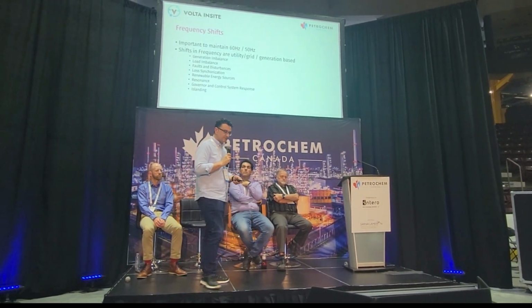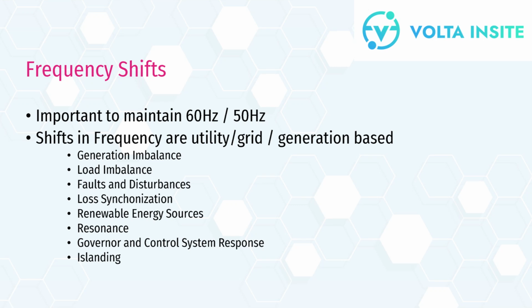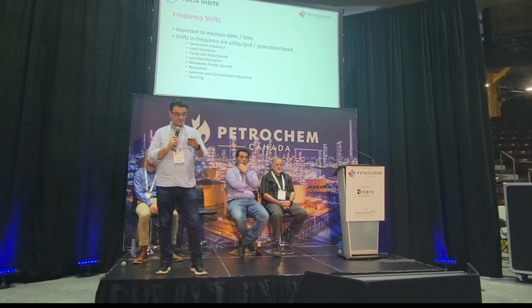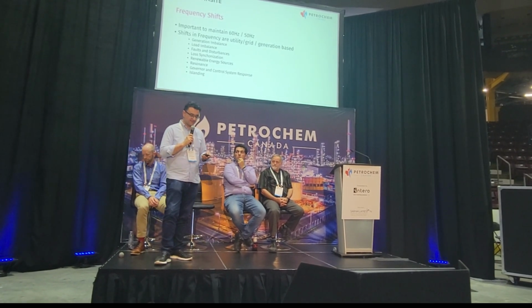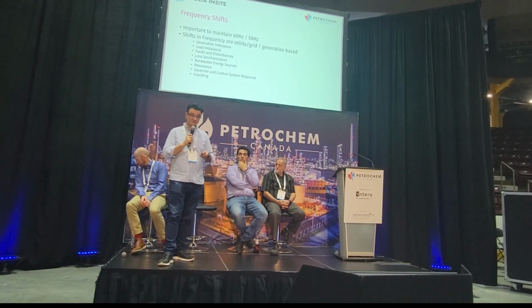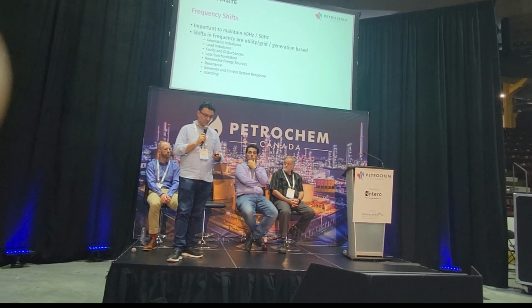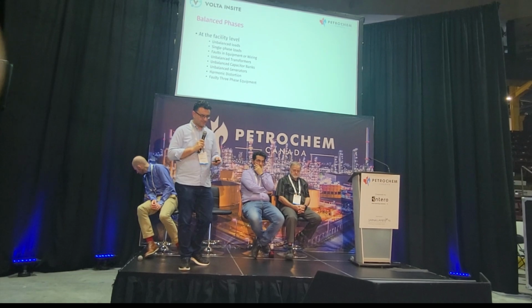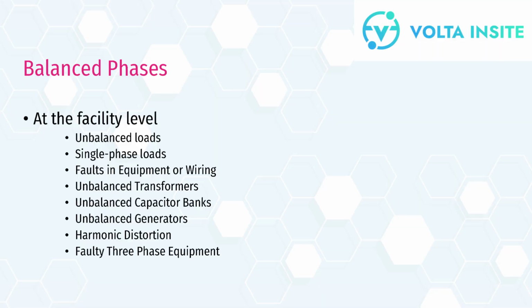There's also frequency shifts that may happen, and that's usually a direct consequence from the utility. A lot of it has to do with renewable energy sources and some big heavy loads where the utility can't handle it. And then there's balance phases, and this is more on the commercial side.